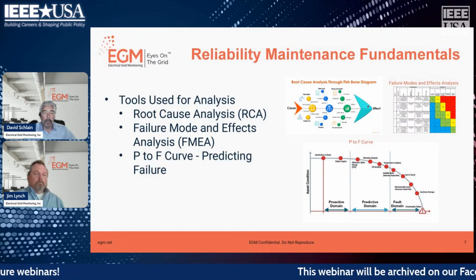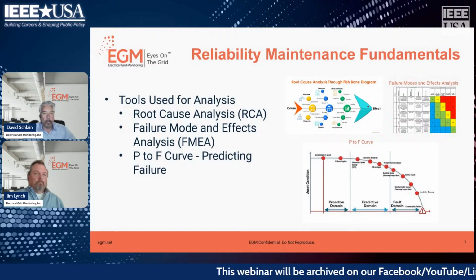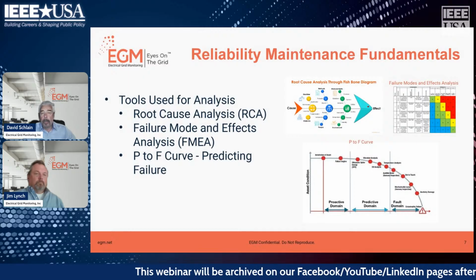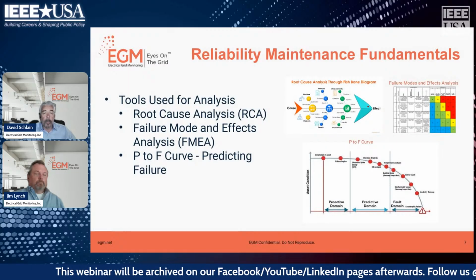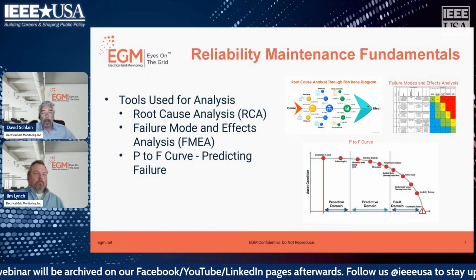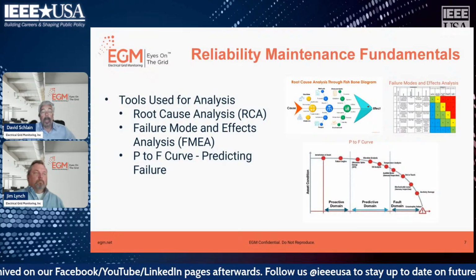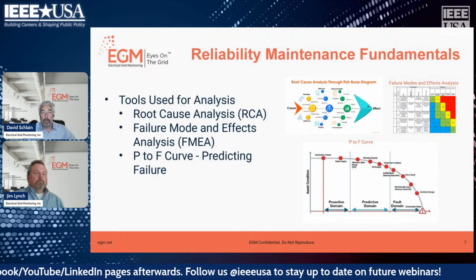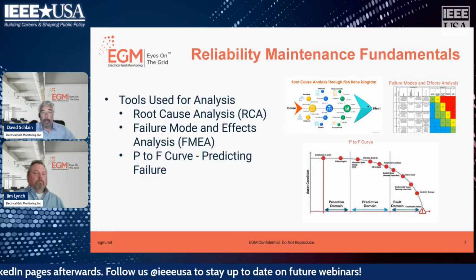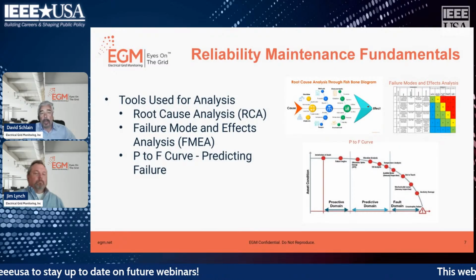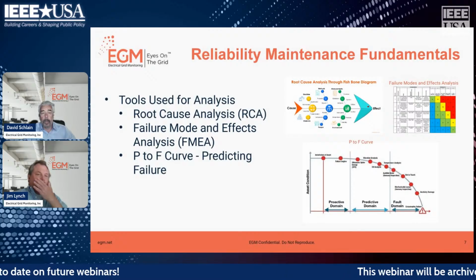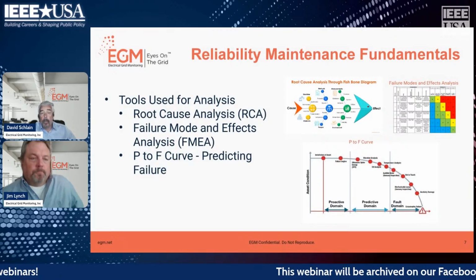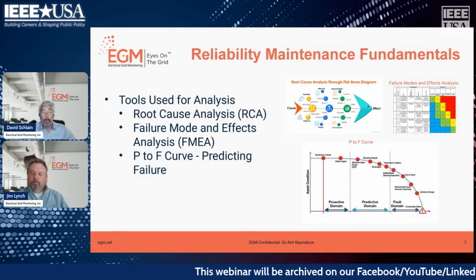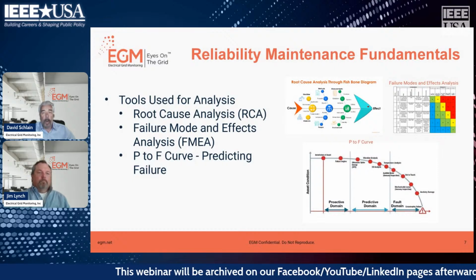Also, when trees rub or lay on lines, they cause arcing or momentary faults that are usually cleared with protective devices like fuses or reclosers. If we can measure the frequency of these momentary faults and correlate data like wind and satellite imagery, we can get a clearer understanding of a potential issue that could cause an eventual power outage. So identifying and locating these events can help utilities prevent failures, and again move their vegetation management program from time-based to proactive.